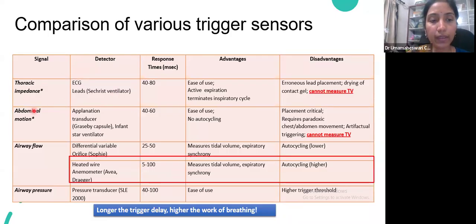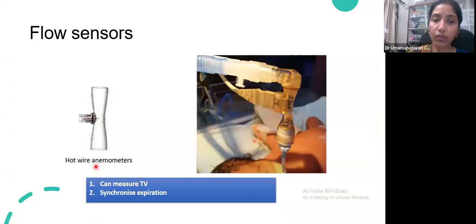Though thoracic impedance and other Graseby capsules are very simple, the main disadvantage is they cannot measure the tidal volume. We will learn in subsequent sessions how important it is to measure tidal volume, because in your hybrid mode, you will be using tidal volume. So majority of the time, we use the hot wire anemometer. There are newer sensors like NAVA also, which can trigger and sense in a very accurate manner.